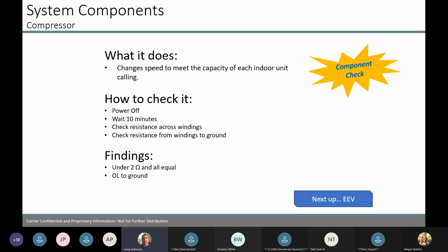Any of these units, when we're working on them and we're going to test them, we're dealing with 3-phase DC voltage in a lot of the units. Make sure they power off and let those capacitors inside drain out. We could get an electrical shock. So we're going to check the resistance across the windings, and we're going to check the windings to ground. So we're going to make sure they're all under 2 ohms and equal, and we're going to look for OL to ground.